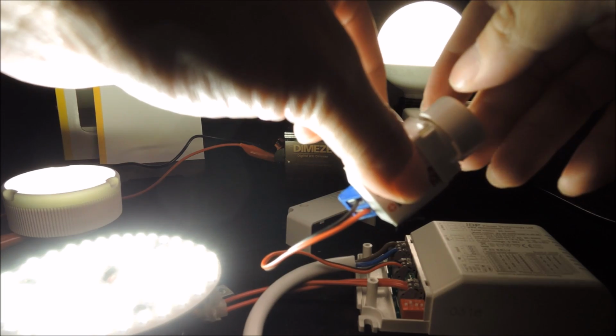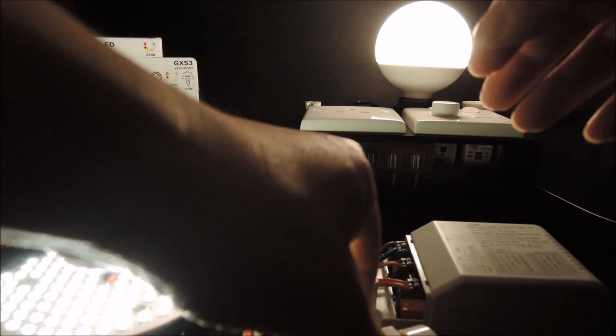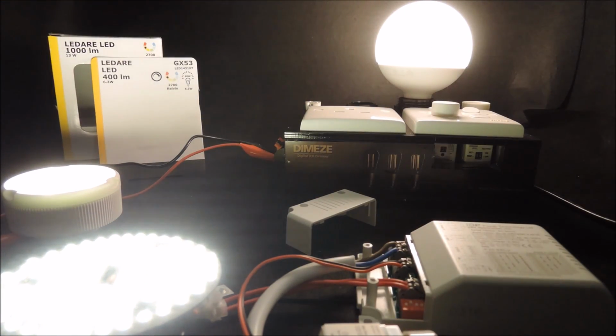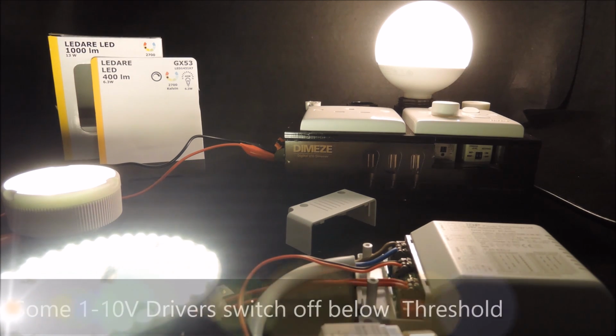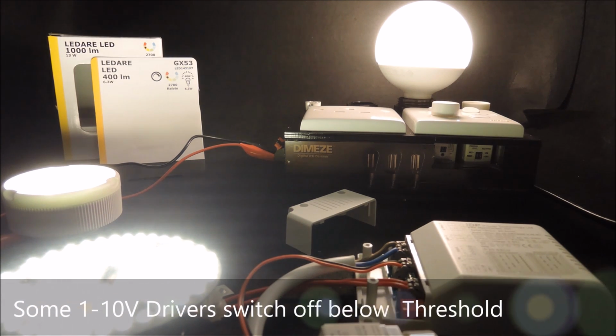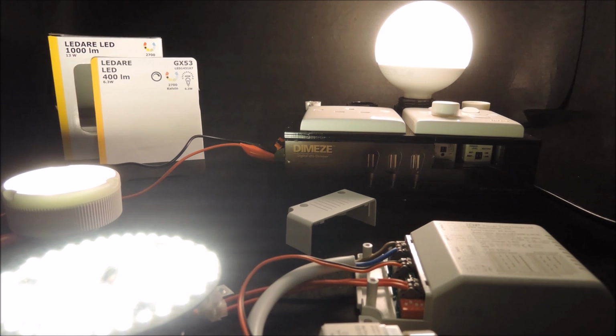However, this is a common practice for replacement projects that basically do not accept any changes to whatever has been installed. Note that some 1 to 10 volt dimmable LED drivers will switch off the lamp if the control level drops below a threshold. So the final performance may also be subject to the combination of the dimming control unit and the LED driver design as well. So for those who have this particular kind of requirement for your application, please check with your LED driver manufacturer if such function is available.